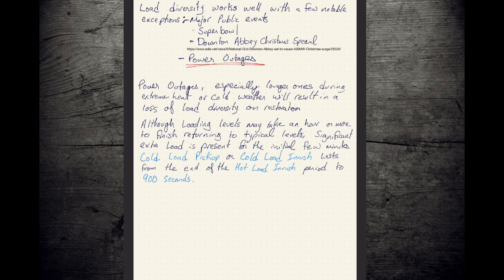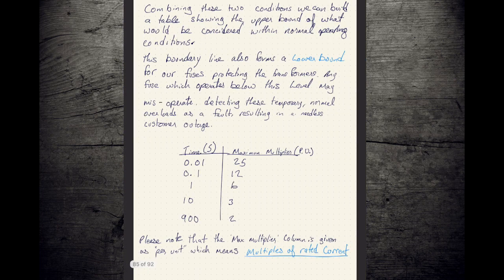This is called cold load pickup or cold load inrush, and it lasts from the edge of hot load inrush, so from about a tenth of a second out to, we call it 900 seconds or so. So if we combine these two, what we end up with is a lower boundary, right? A line, a set of conditions where you do not want your fuse to operate underneath this level. Whatever fuse you pick to protect that transformer or that set of lateral and that set of customers, it cannot operate underneath this inrush boundary.